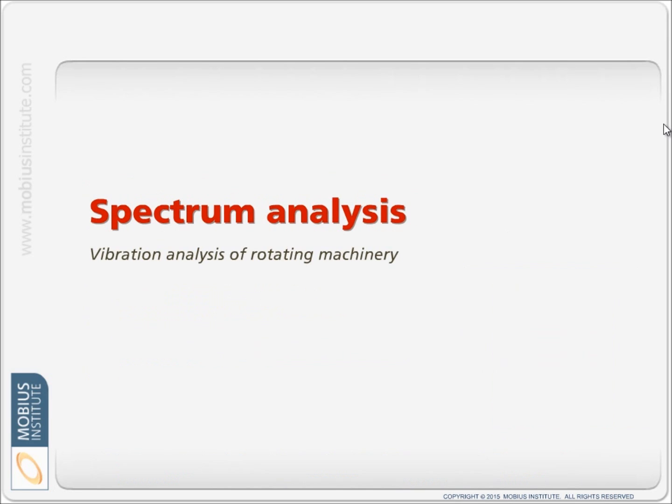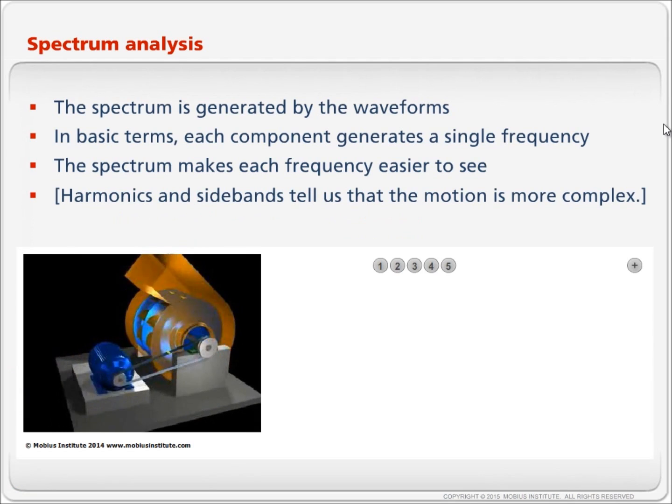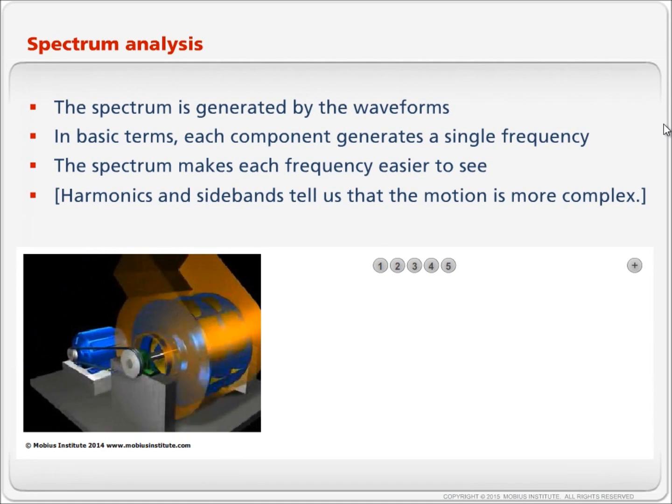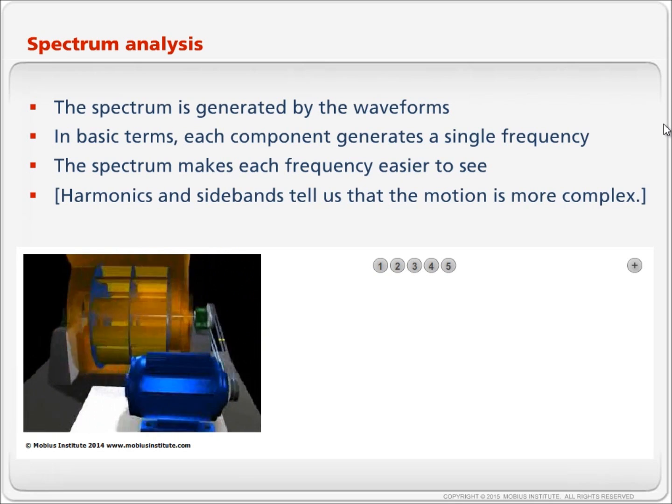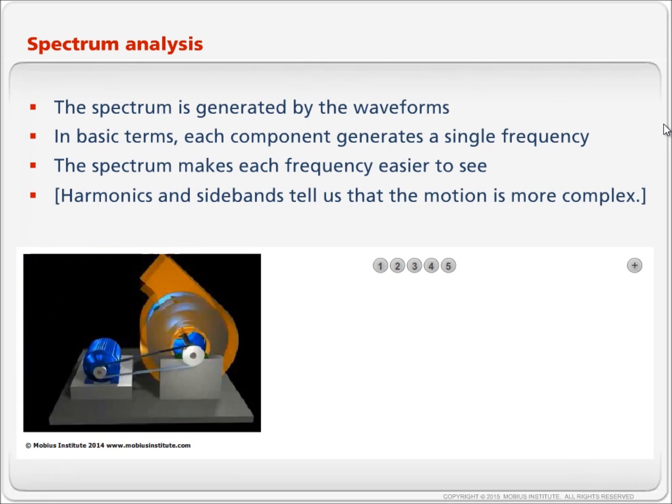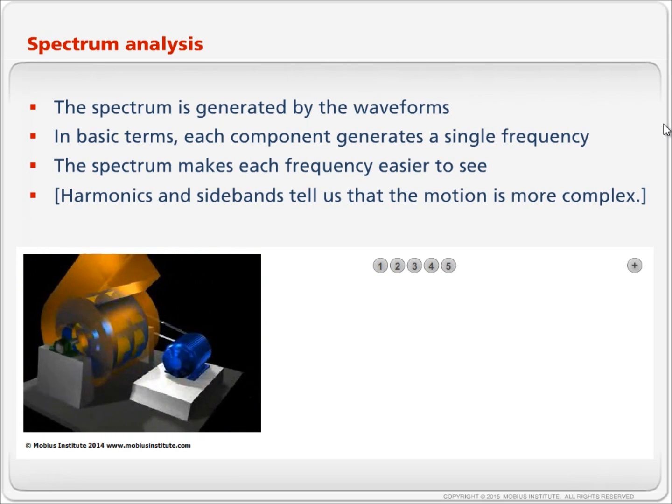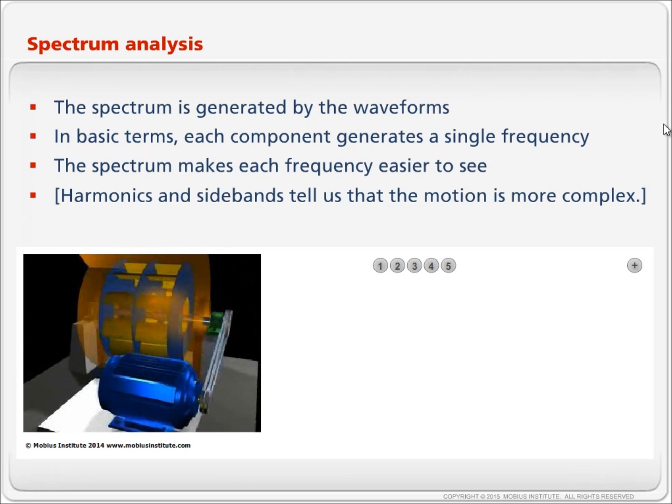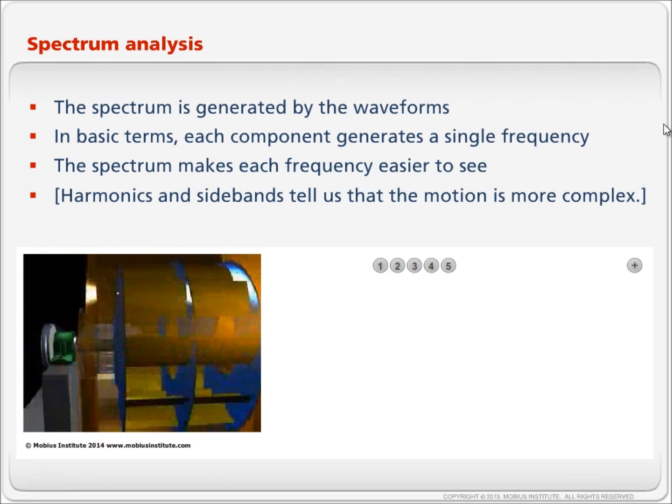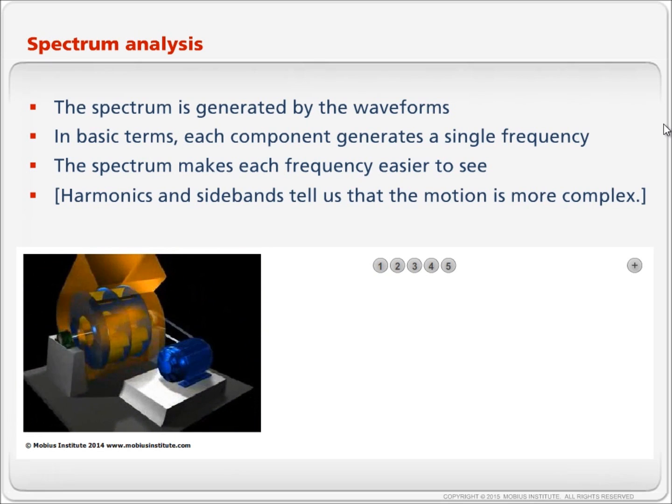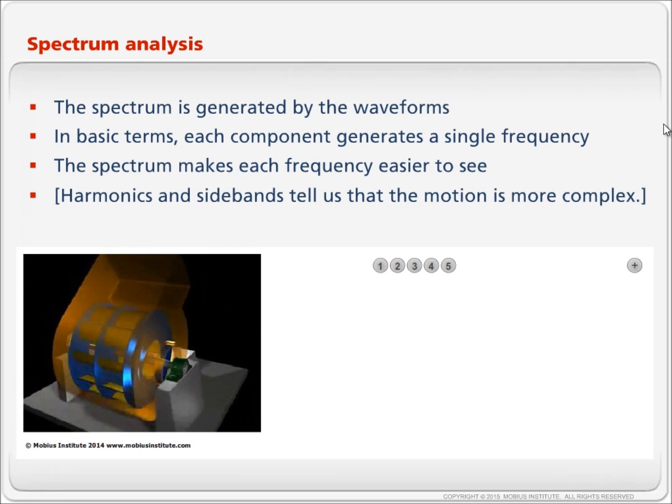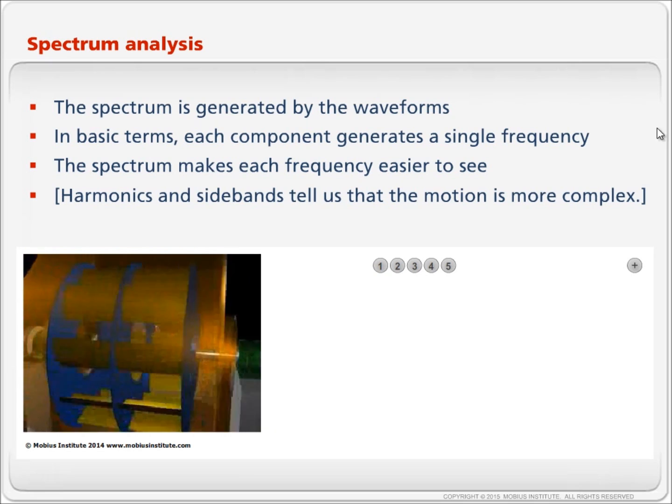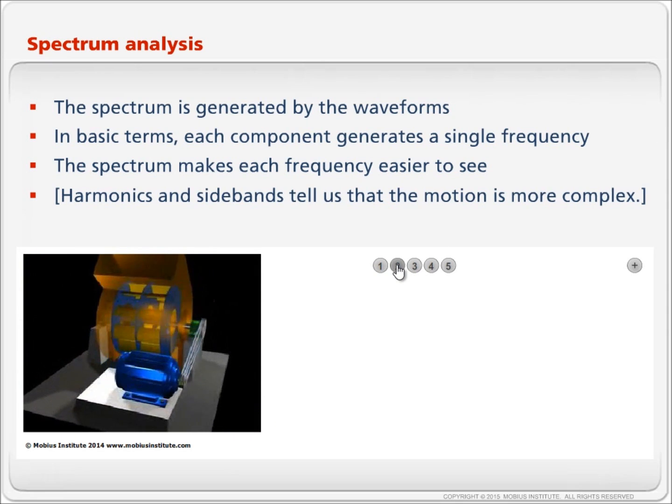So first let's take a quick look at Spectrum Analysis. The spectrum is generated by the time waveforms from the machine. In basic terms, each component in the machine generates a single frequency. The spectrum makes each frequency easier to see. Harmonics and sidebands tell us that the motion within the machine and the forces involved are more complex than simple single frequency vibrations.